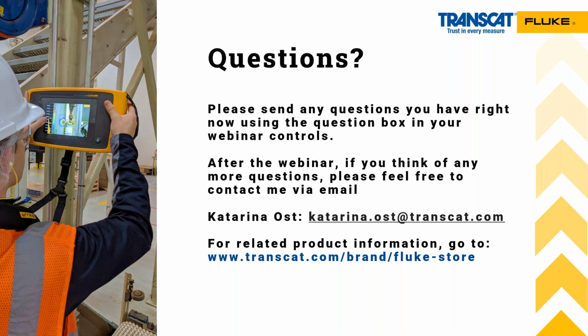There are what are known as arc flash ratings and arc blast ratings on IR windows. We can go as high as a 63 kA arc blast, and we're rated up to 72,000 volts. There's background information, and if this individual would like to talk more about it through Katarina, we can arrange that and share all the data on ratings and application of the windows. There are proper procedures that have to be followed to install the window correctly, but we have that spelled out in great detail, and it doesn't take long at all—a number of our series windows can be installed by one person on one side of the panel in 5 minutes or less.